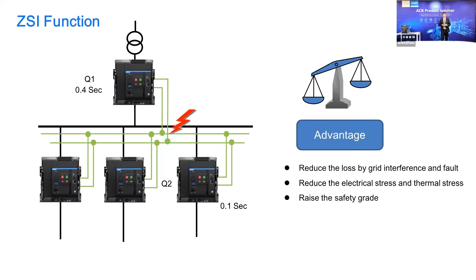If the fault point is here, Q2 doesn't have any signal because the fault is on its upside. So Q1 hasn't received any message, so Q1 will trip immediately. This is called ZSI. It is very useful for selectivity. For our designs, selectivity is used more and more widely. This is one kind of ACB selectivity.